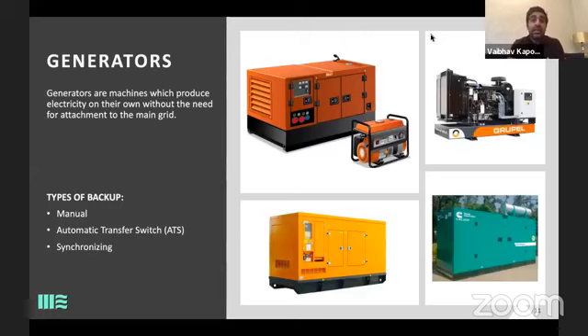Manual changeovers are totally unreliable, they are unsafe, and they are not meant for outdoor use because they are open from all ends. Most of the time, our changeovers are kept outside where the generators are parked. It could rain, people could cross. So manual changeover is not suggested. The second type of changeover, which we are also using and which is available in the market for everybody, is the automatic transfer switch. Automatic transfer means that you don't need any human involvement. As soon as your main genset goes off, it automatically shifts to the other generator without any human involvement.